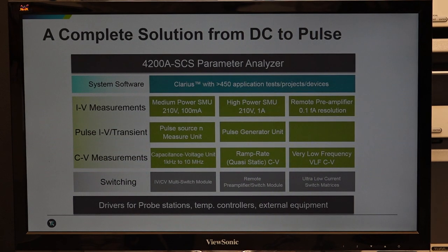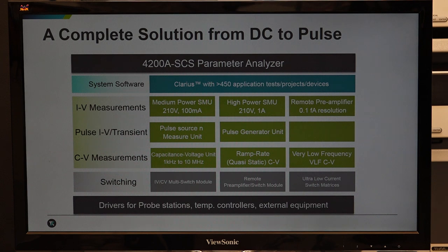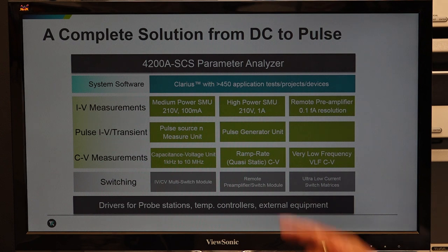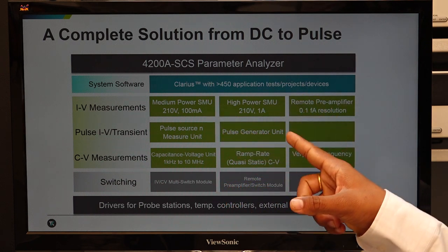Model 4200 is a configurable platform with a built-in industrial PC running Windows 10 and a powerful software called Clarius. This software has many routines to control internal hardware and also supports control of external hardware like probe stations, external temperature controllers, optical sources, and magnetic sources. For IV measurement, various types of SMUs are available — medium power SMU or high power SMU.